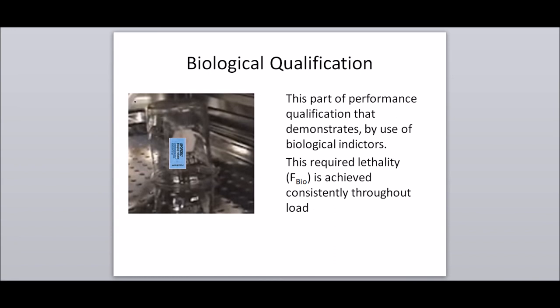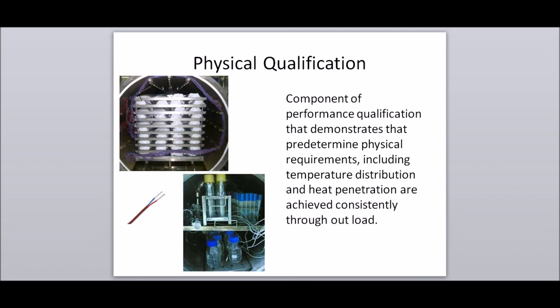Biological qualification: the part of performance qualification that demonstrates, by use of biological indicators, that the required lethality is achieved consistently throughout the load. Physical qualification: the component of performance qualification that demonstrates that predetermined physical requirements, including temperature distribution and heat penetration, are achieved consistently throughout the load.